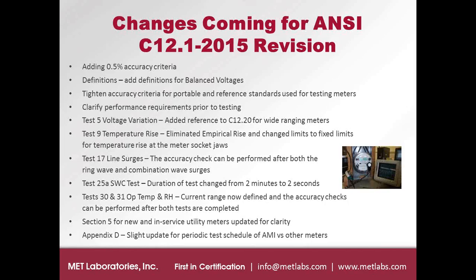I mentioned earlier we run an as-received set of tests that determine the accuracy of the product before any external influences or any tests are run on it. And there's been some clarity added to the standard to help folks understand what the criteria is getting into a test program. So test 5, test 9, there's been some changes there, eliminating the empirical rise calculation that is currently in the existing document, going more with a fixed limit for temperature rise, with some direction on where to measure those rises on the meter jaw, the meter socket jaws.